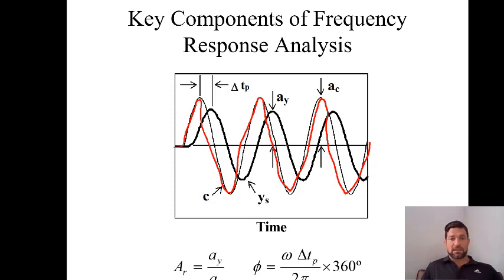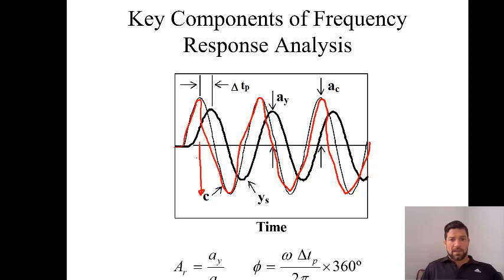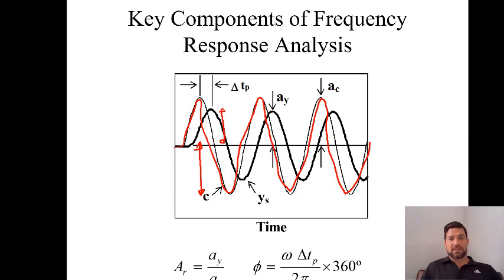There are two important characteristics of this type of response. First, there is an amplitude associated with the sinusoidal input and an amplitude associated with the sensed value. The important parameter called the amplitude ratio, AR, is a measure of the amplitude of the output over the amplitude of the input. The other important term is the phase angle, which is the difference in phase between the two signals. A phase angle of zero means perfectly in phase; 180 degrees means perfectly out of phase. The distance between the two peaks tells us the phase angle.